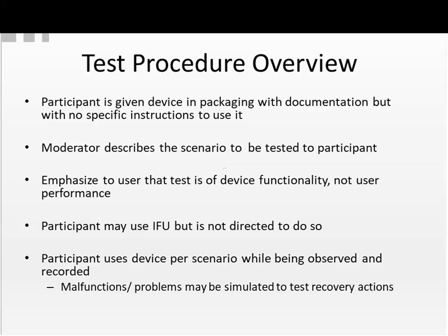During a test, the participant can use the information for use, but he's not directed to use it. It's his choice. The participant uses the device per the use scenario that's being tested, and he's observed and he's recorded.